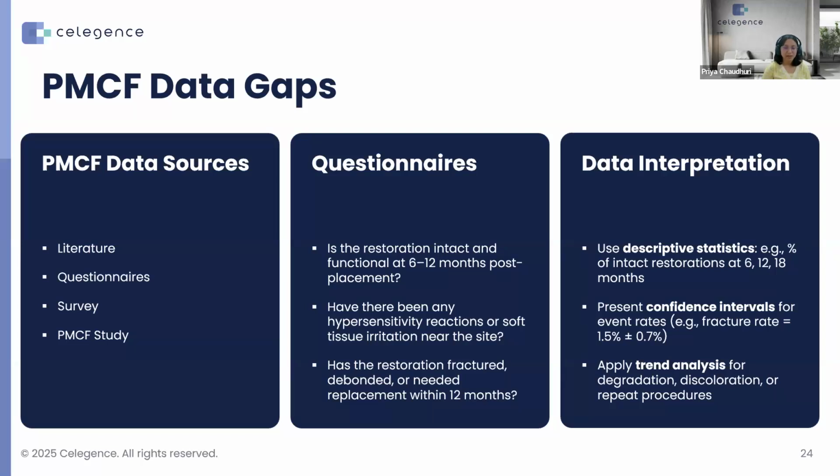So as Manaswita mentioned, it was a class 2A implantable dental restoration device. If you see on the left, we could see a few typical PMCF data sources which similar device manufacturers can follow, which are the targeted literature on similar devices or materials, especially driven to the performance and safety criteria that we have. Then structured questionnaires, of course, sent to clinicians or patients, surveys to track usability, and in some cases, prospective PMCF studies can also be planned, particularly when durability or the risk tolerance is being monitored for a longer duration.